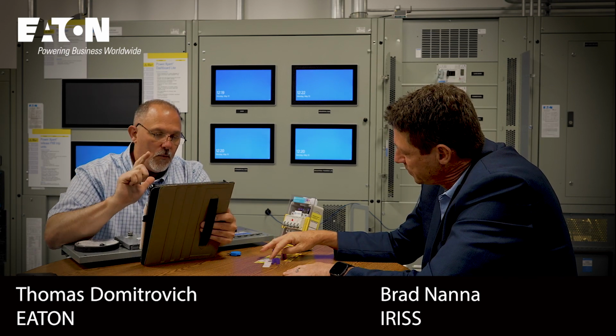All right, we've covered a lot. We covered 70B, chapter 9, frequency of maintenance. We talked about continuous monitoring and predictive techniques, the arc flash boundary, IR inspection windows, the Safe Connect thermochromatic paint, and the eSentry Asset Management software. The code also says you have to have a documented program—that's 70E. If you exercise your maintenance, you develop your electrical maintenance program, and it has to be documented.